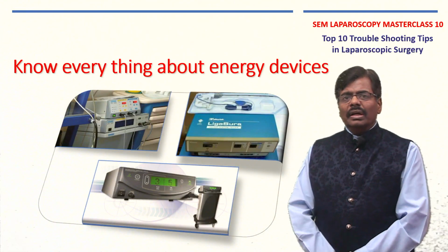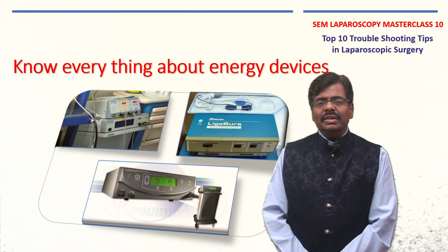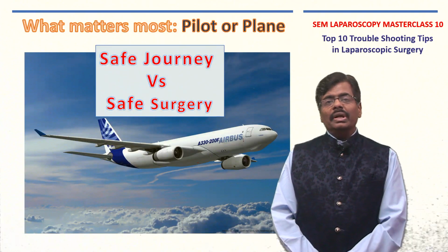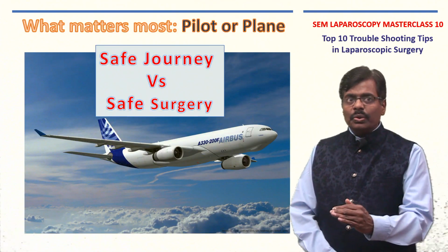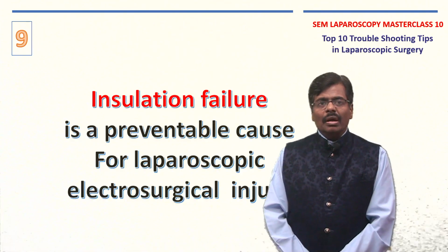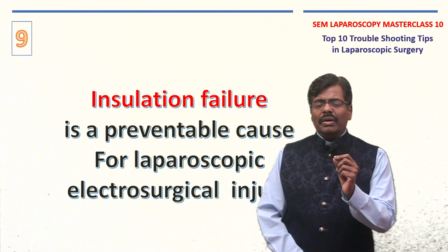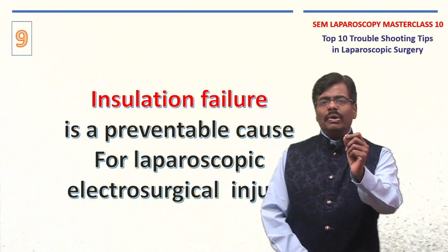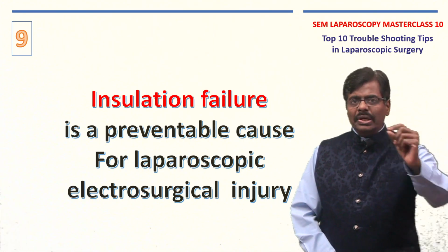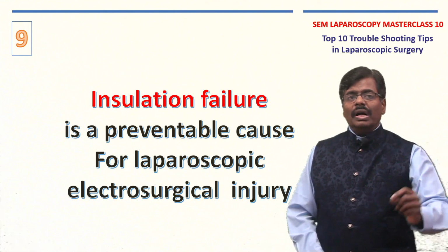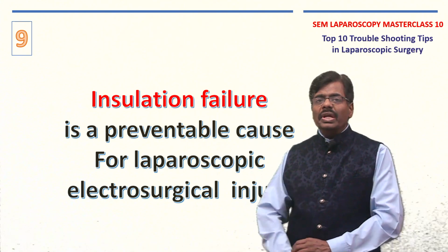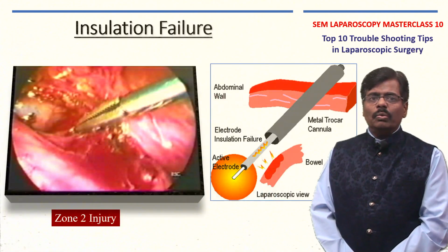And coming to the next couple of tips, energy devices, if they are used properly, can make sure that you have a safe surgery. One of the important things I wanted to tell you is to inspect your energy sources, especially the insulation of all the equipment. Otherwise, you get into this problem of insulation failure whenever you use a monopolar diathermy.